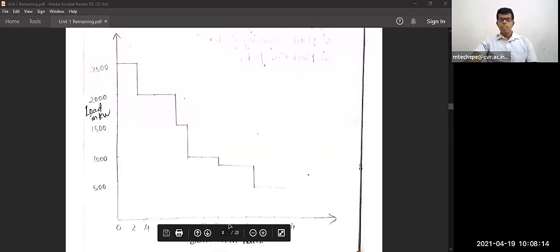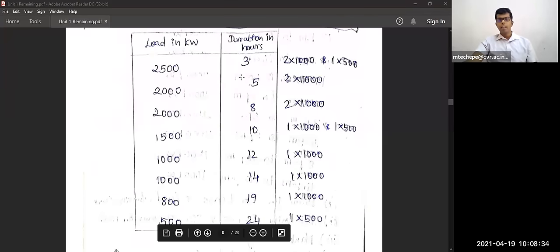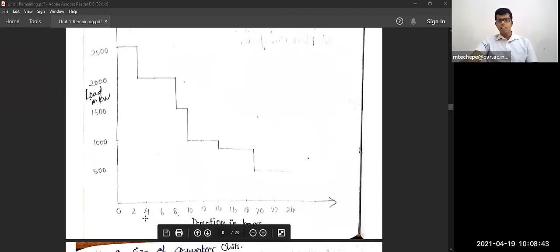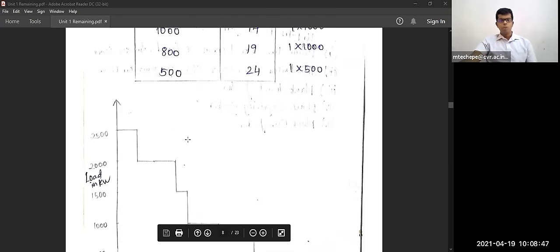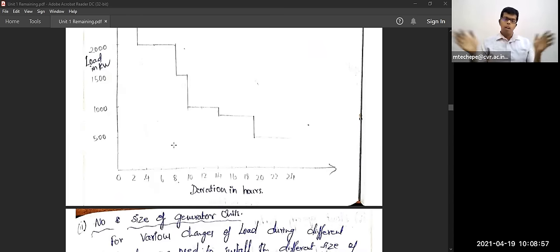Using this sorted table, you can easily plot the load duration curve. On the load duration curve, you can quickly see the maximum demand and how many hours each load level persists — for example, 2500 kW for 3 hours, 2000 kW for 5 hours, and so on.